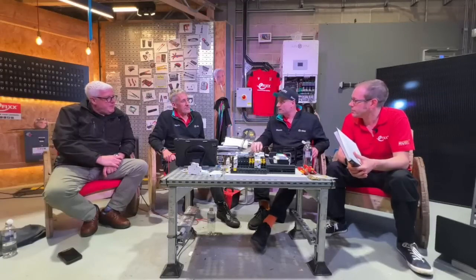So again, it's recommended on all socket circuits up to 32 amps. Remember, that's the socket's own value, not the actual value of the breaker size. So it's all about protection and safety. We're not saying the regs say it's got to be done for any reason other than the protection of people and the protection of property.